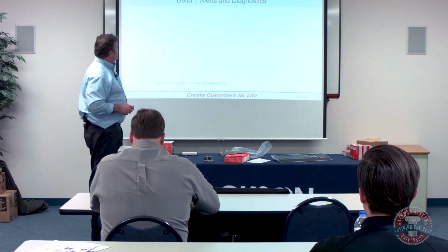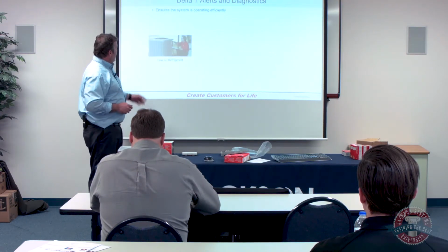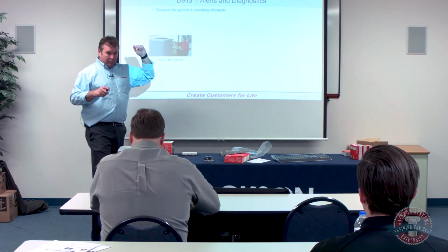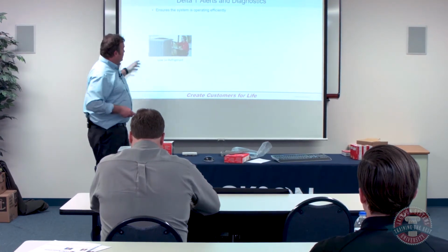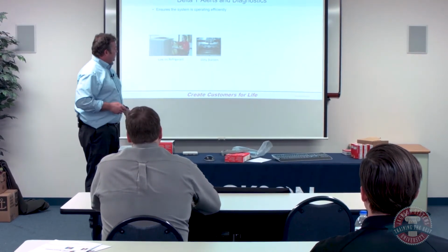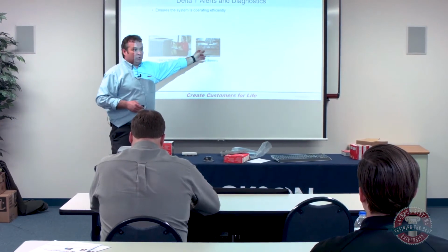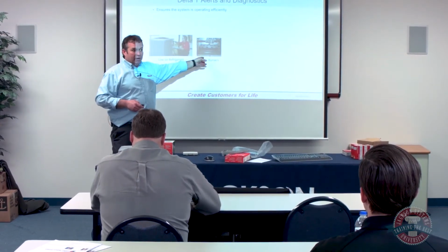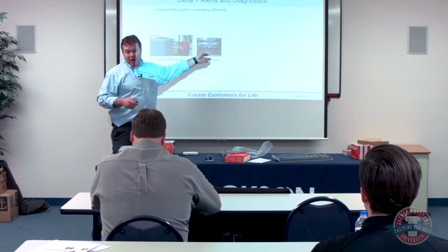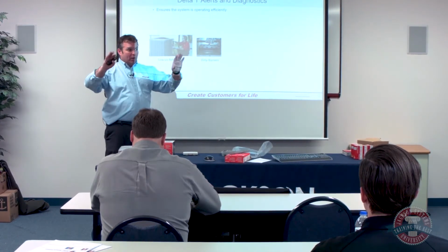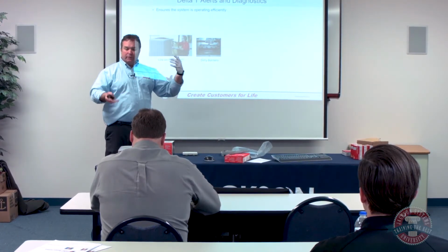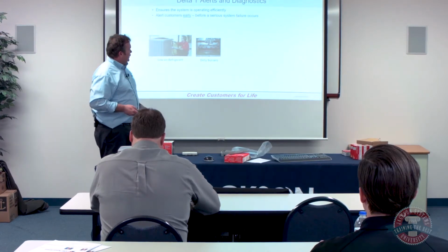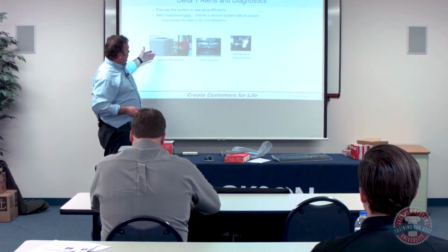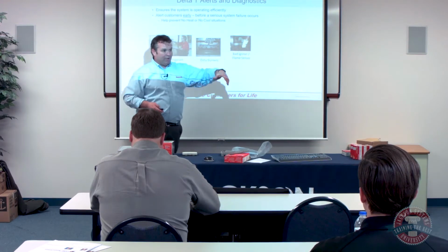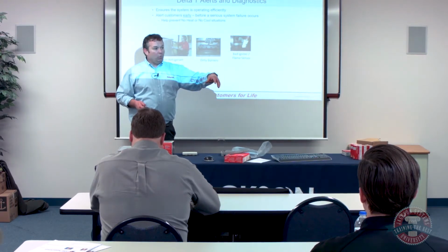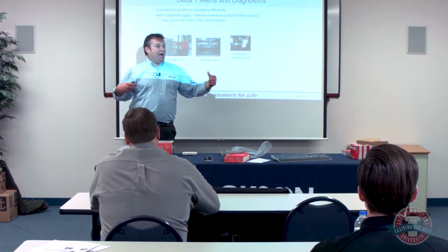So if I've got the delta T, remember I said you could put a supply and return sensor in, that delta T is going to tell me if I'm low on refrigerant, if I've got a dirty furnace, burners not running right, a cracked heat exchanger, a flame rollout, or going off on internal overload. All that stuff gives me a reason for that alert to come to me instead of the homeowner walking into a hot house in the summer.